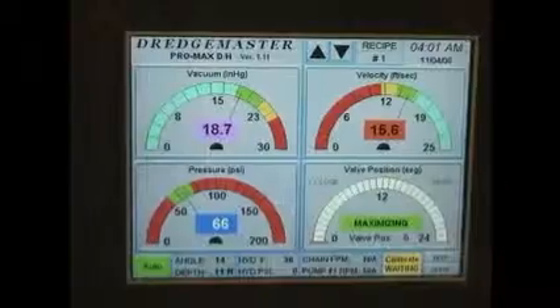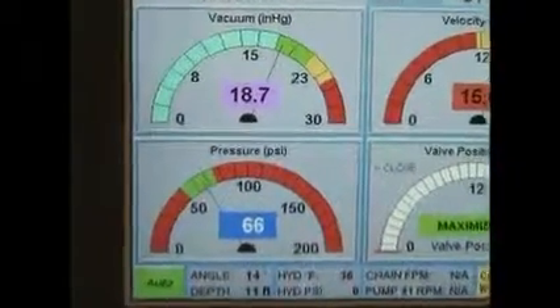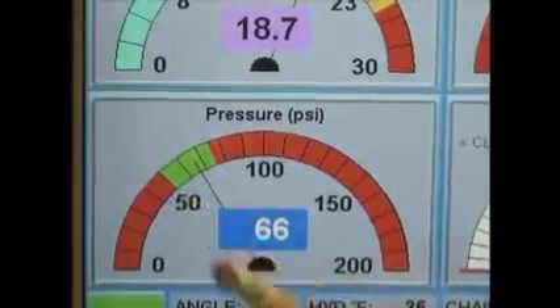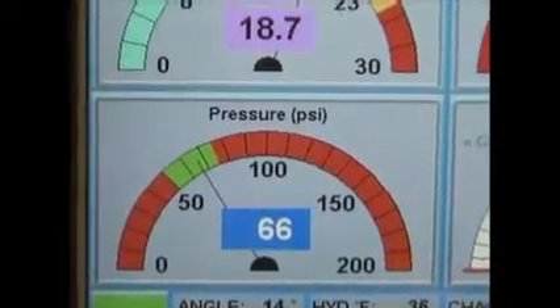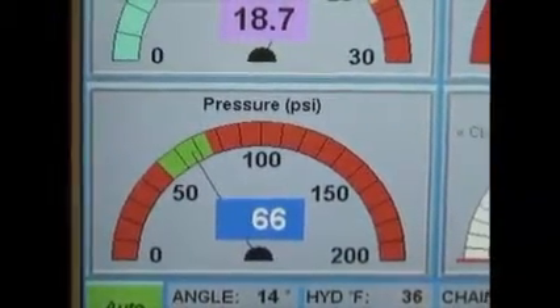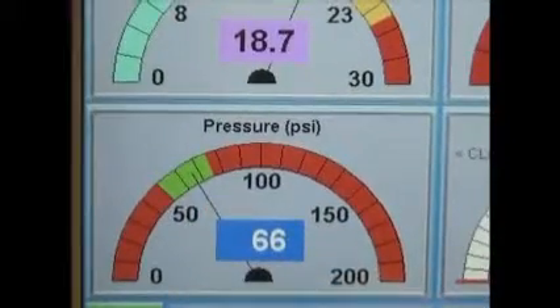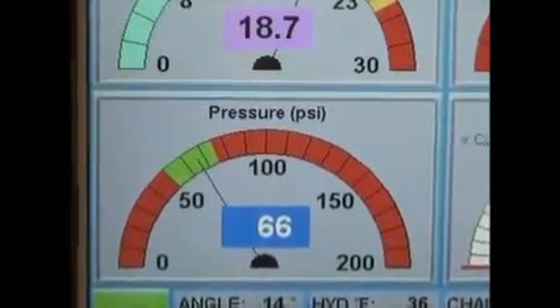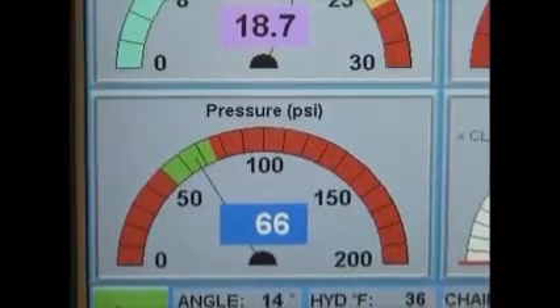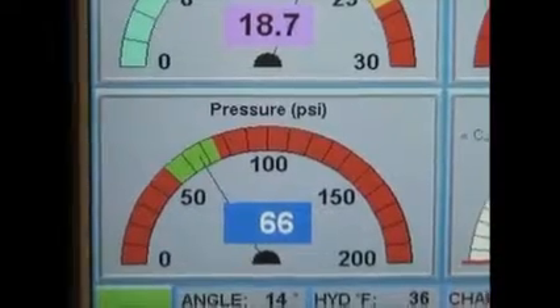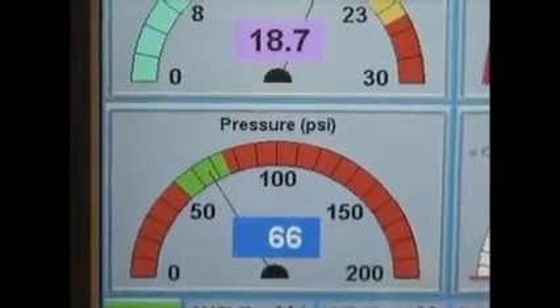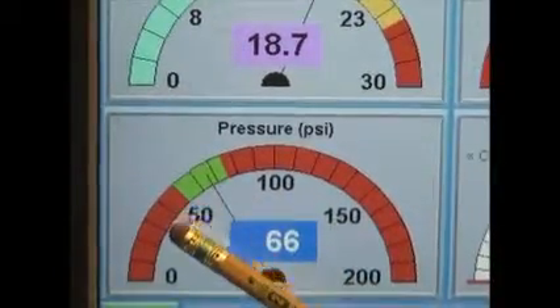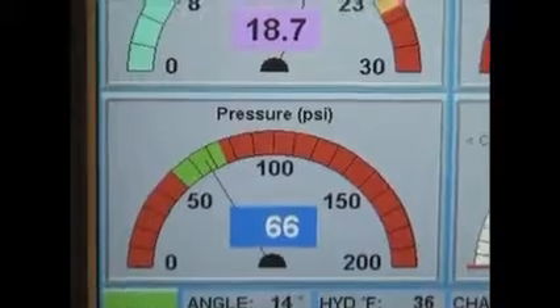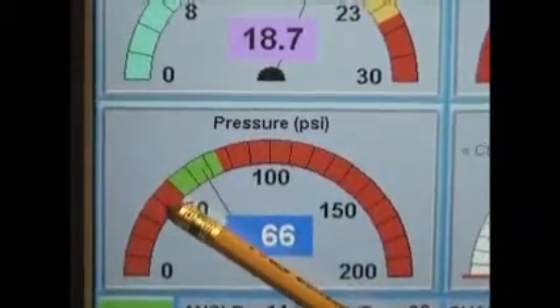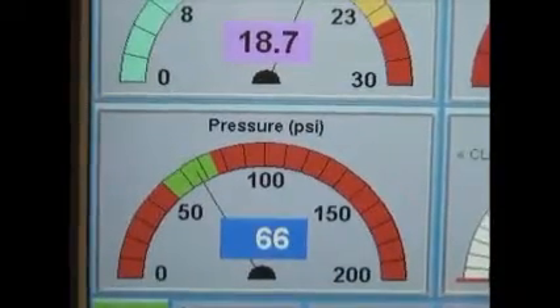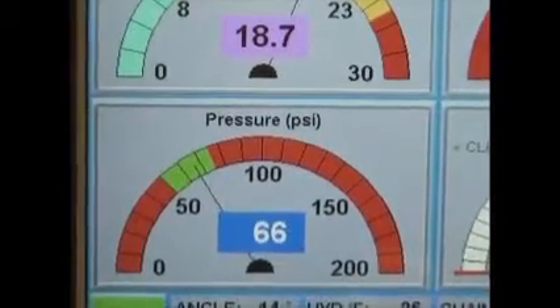The pressure gauge is a little different, and all we have is 2 colors. We have a red zone and a green zone. The green zone is the area where you want to set your pipeline discharge line pressures to normally operate. As we can see, we have a red zone to the left of our green zone. If a pump starts to cavitate, what happens is that it starts to recirculate material inside the impeller. When this happens, the pressure usually drops below a set point. If that recirculation or cavitation issue occurs, we're going to sense that drop and we'll get into this red zone area. When the valve goes into the red zone area, it's immediately going to open the valve fully.